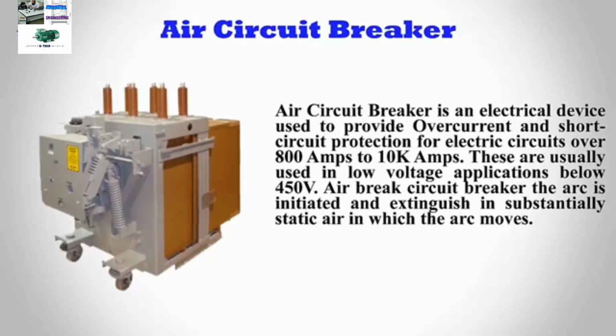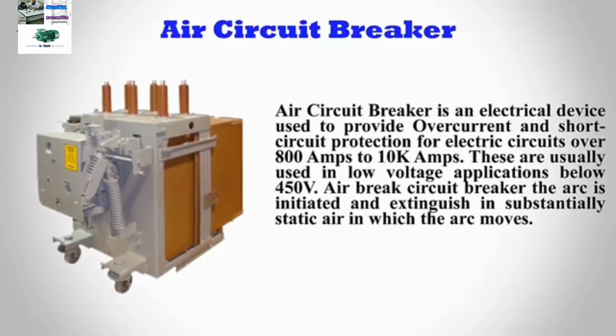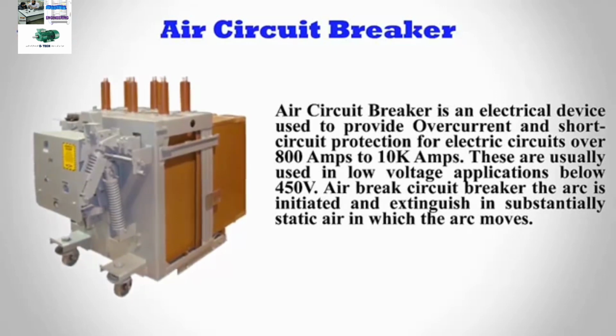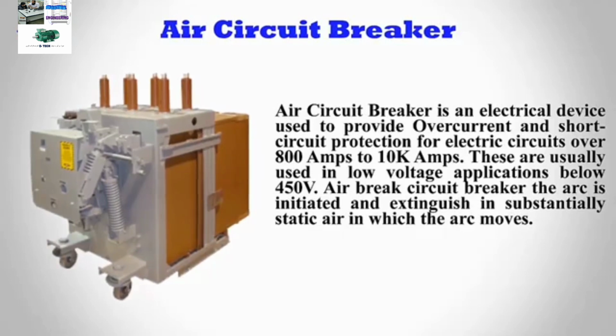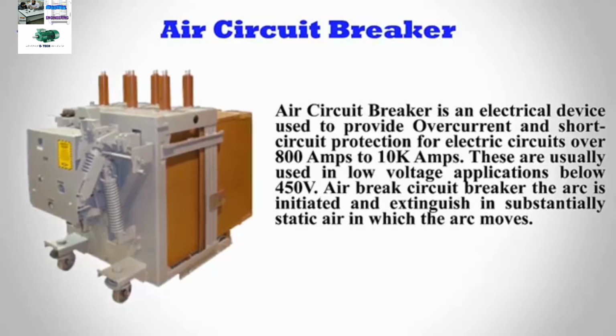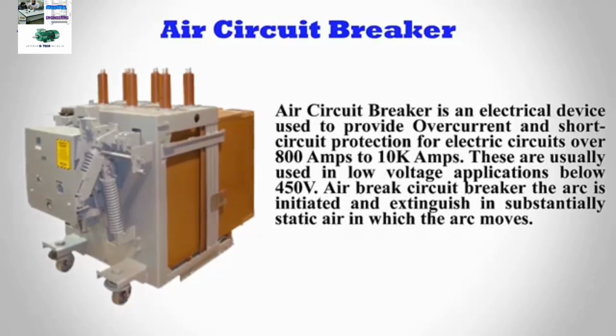An air circuit breaker is an electrical device used to provide overcurrent and short circuit protection for electric circuits over 800 amps to 10k amps. These are usually used in low voltage applications below 450 V. In an air break circuit breaker, the arc is initiated and extinguished in substantially static air in which the arc moves.